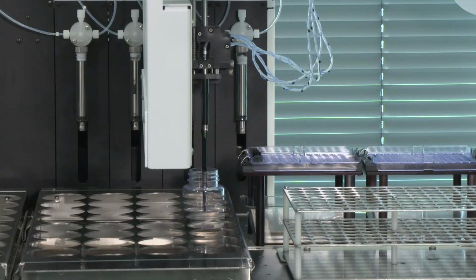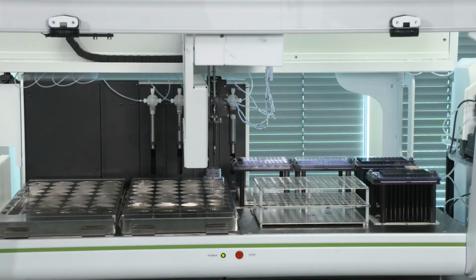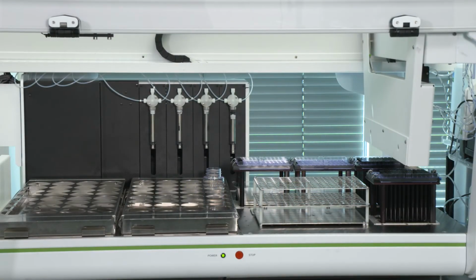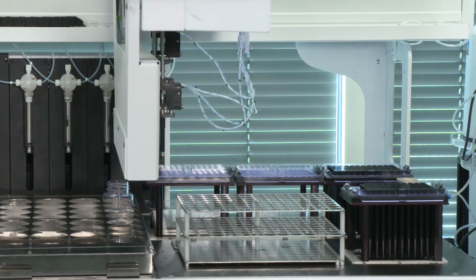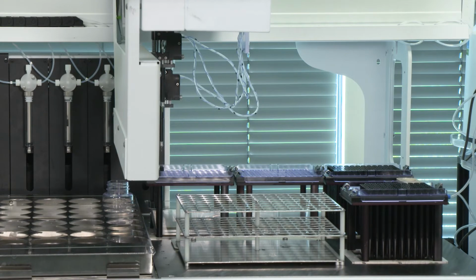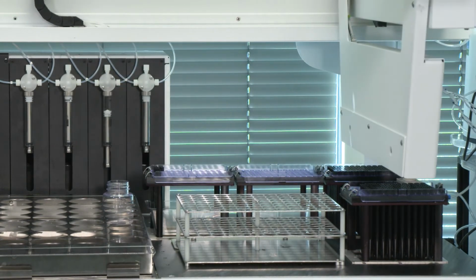Aspirate the sample. Dispense the sample. Clean the lines and replace the tip in the used tip tray. And then after that, it will give us an indication as to whether or not the Pathlength was in the acceptable range.